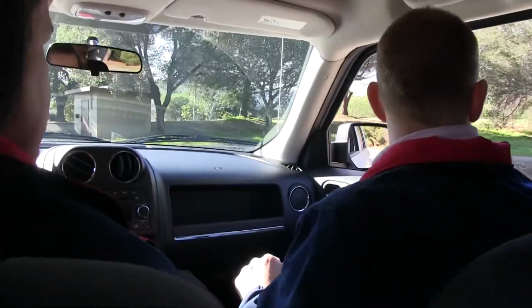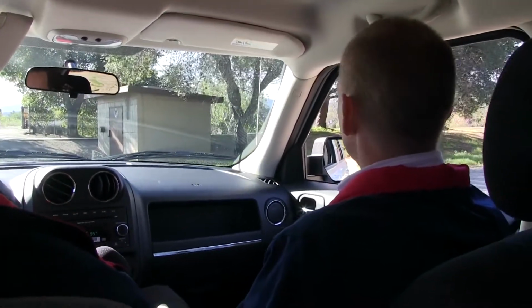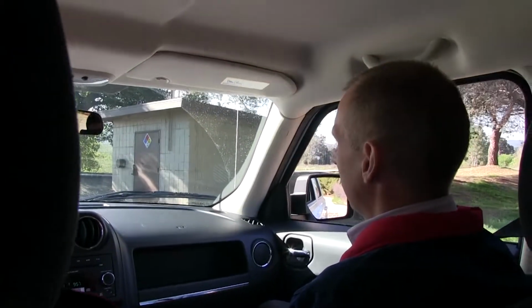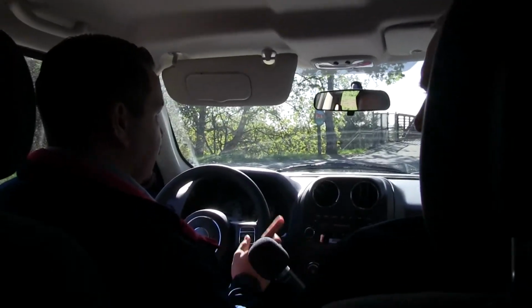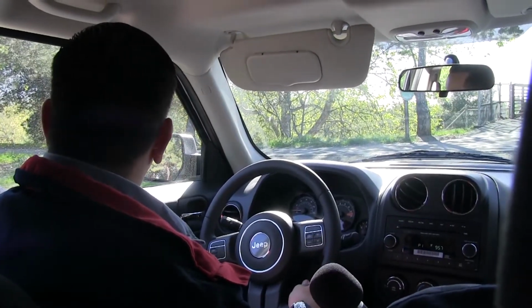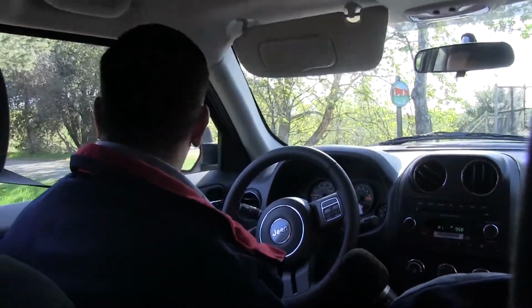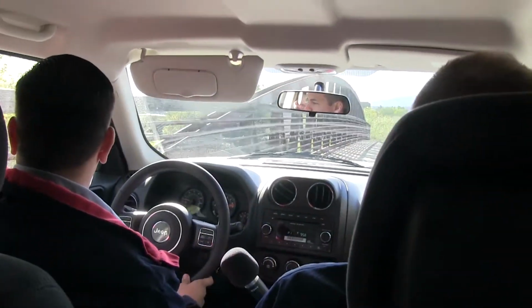Is this another stream gauge here, 53? Yes, that's one of our stream flow stations. Basically, the water comes in at this. We got the turnout that's across the way, and then where we're going to go to is the Kirk Dam, where we can pull the water off the creek. This building right here is the chemical feed station, which I was mentioning. So we'll inject it with the poly, and the poly will grab all the sediment, make it real heavy, and drop out into the bottom of that desilt basin. And here's Los Gatos Creek right below us.